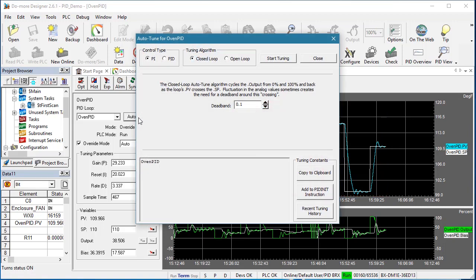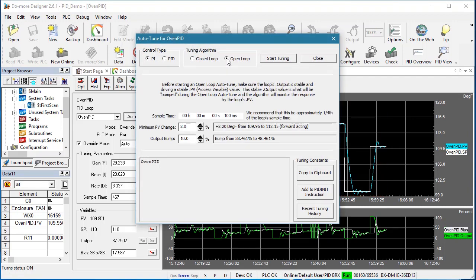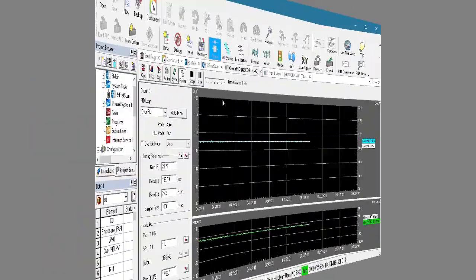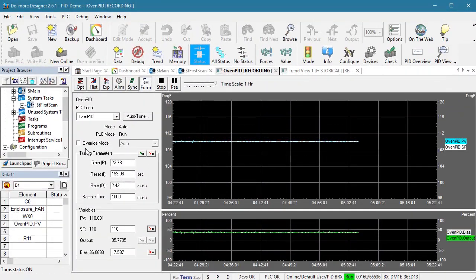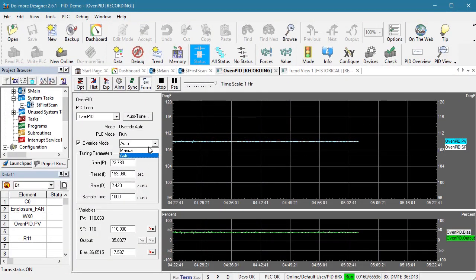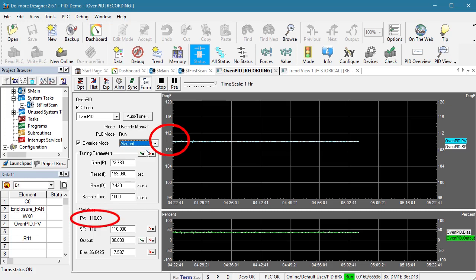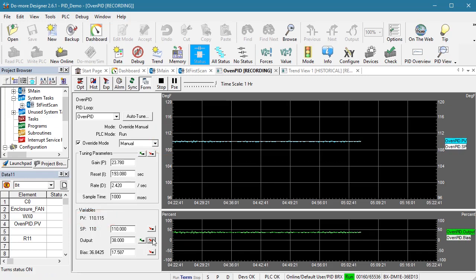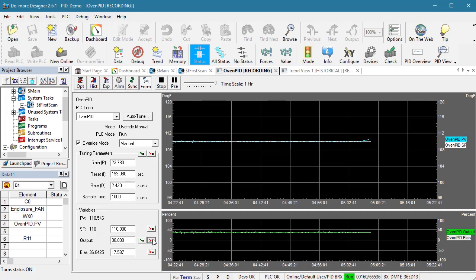One more thing. Did you notice that the Do More Designer has an open loop tuning option? Let's try it. But before we start, we need to make sure we are in manual mode so we have a fixed PID output and that the process variable is settled out near the value we want to operate at. This is critical to getting open loop tuning to work. If you are in Auto mode when you start open loop tuning, the PID output will be jumping around doing its PID thing and it will confuse the open loop Auto-Tune. You can see where I switched to manual. The PID output stopped adjusting things and it got real flat.